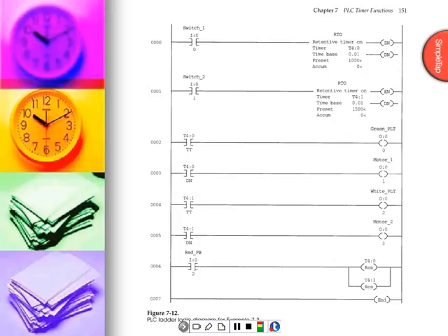Alright, same thing with 2. I throw switch 2. I count off 15 seconds. Or actually, while I'm counting off 15 seconds, the white light is on, right? Nothing else, just the white light. If I halt it somewhere in the middle, everything just stops where it is, and restarts as soon as I close the switch again. Now back to my scenario in Alaska, I could reset it. But I'd have to remember to reset it before I started the warmer back up.